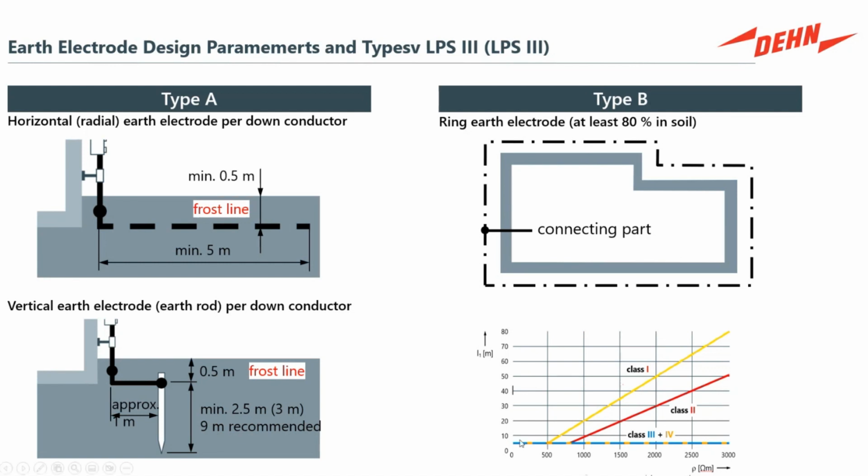So what you'll find in a chart like this below, what you really see here is this 5-meter, this is the length of the rod of the buried earth conductor, and this is the risk based on the soil resistivity. If you have really great moist, high conductivity soil, then you have a derating factor. But as you increase the risk that you evaluate, remember, you start with risk evaluation. If you increase the risk, you need more depth of earth rod, not just to get your 20 ohms or your 5 ohms or whatever the standard might say for NFPA 780 or National Electric Code. It might say, you should have a 25 ohm connection and you should put in a 20-foot earth rod. If you have a higher risk, it's not enough. You need more earth rod. That's to control the risk.